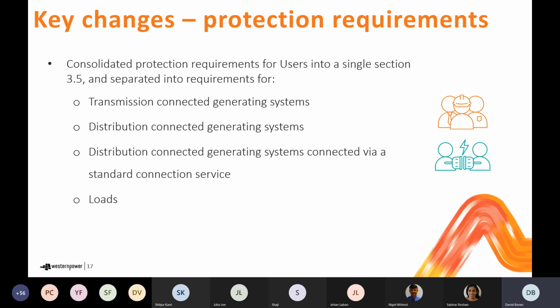So within section 3.5, there's subsections that present common protection requirements, and then additional sections that go in and specify the requirements that are specific to loads, protection requirements specific to transmission connected generators, and requirements that are specific to distribution connected generators. And we also have a section there that talks to the protection required for small generators connected to the LV network via standard connections. So you can see then it's a fairly simple way to navigate and identify which requirements actually apply to any given user facility.